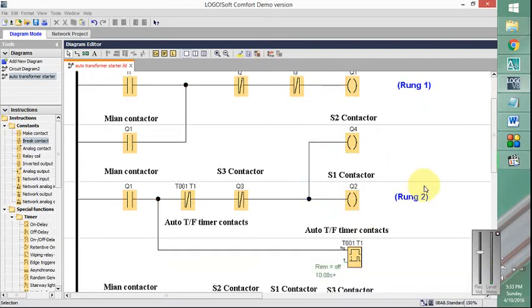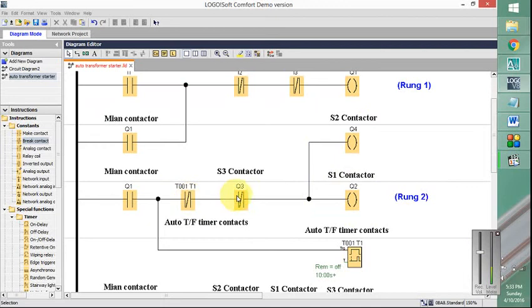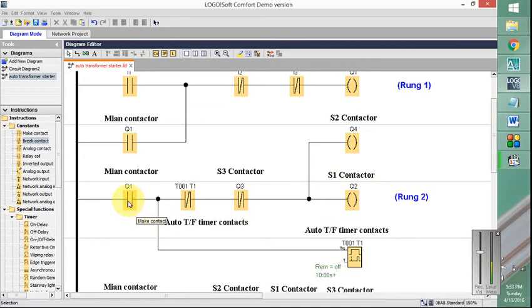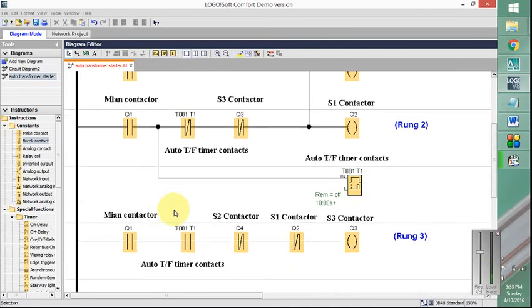Now this section turns on the timer and also energizes the contactors S2 and S1. As you can see, these two will only be energized if main contactor is energized, transformer is not activated, and the third contactor is also not energized. Also, as soon as the main contactor is energized, the timer will start counting the preset delay as you can see it has been added here.